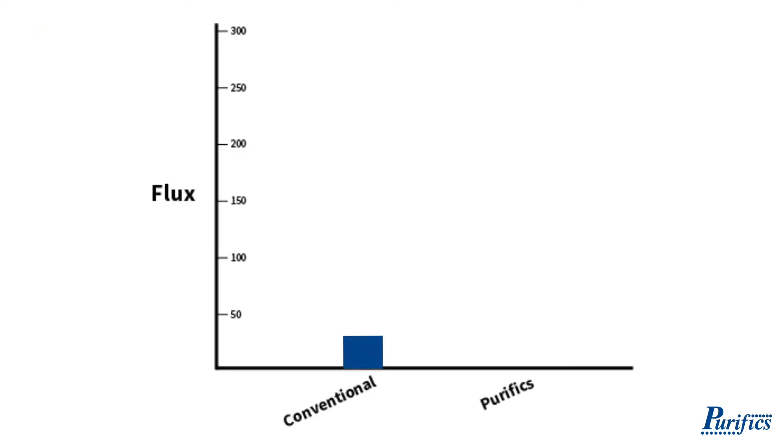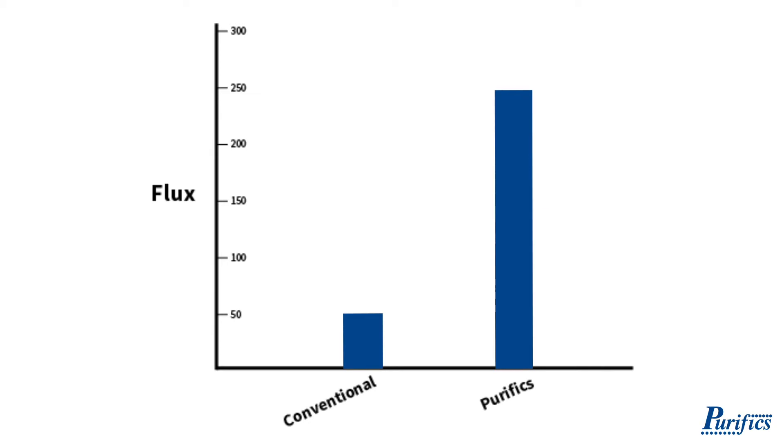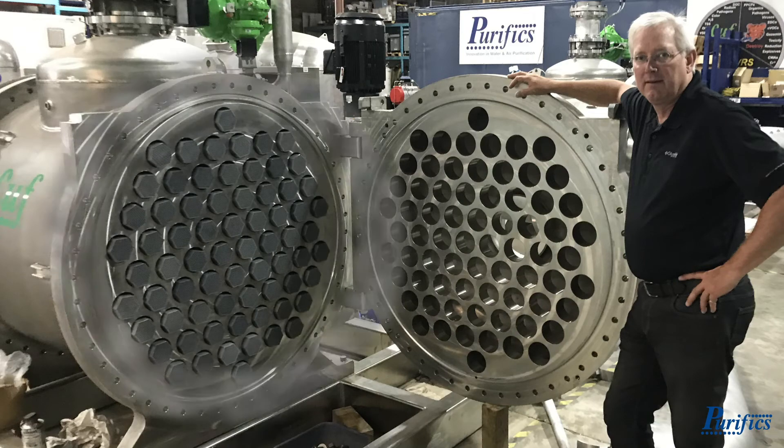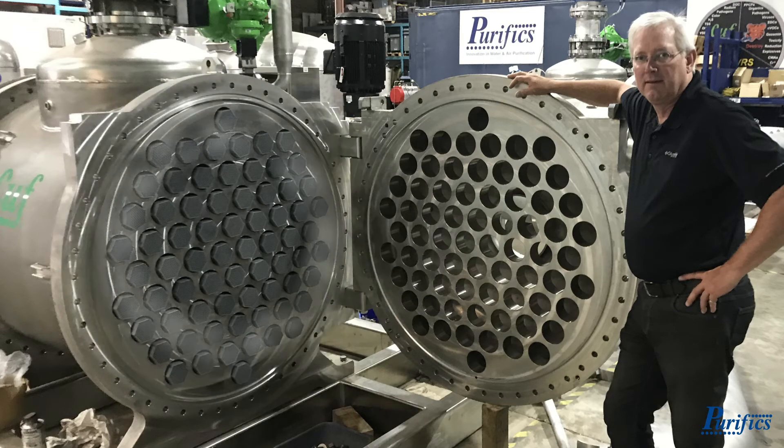Continuous ultra filtration systems operate at five times the flux of other membrane systems, providing better water at lower cost. CUF operates without pre-treatment and does not have conventional backwash, back pulse, or CIP processes due to its unique dynamic shock process. Dynamic shocks send shock waves through ceramic membranes, which self-clean the membranes and inhibit fouling.